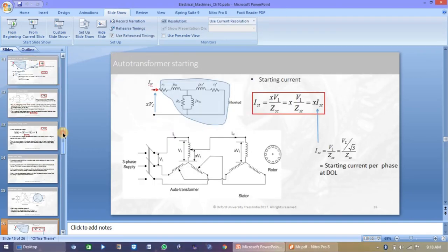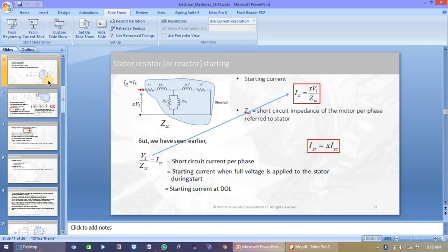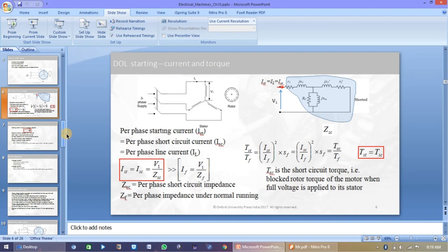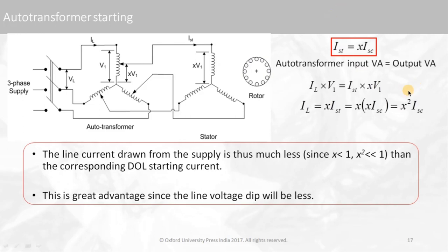To recall, in the DOL starter I_start = I_sc, given by Z_sc. But in the case of auto transformer starting, the x² term appears. So in the case of auto transformer starting, the current is reduced compared to DOL starting — and this is the advantage of the reduced voltage technique.